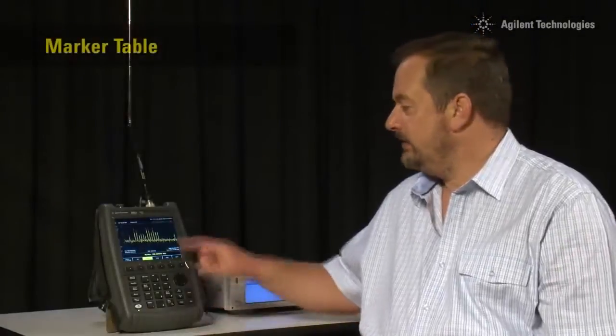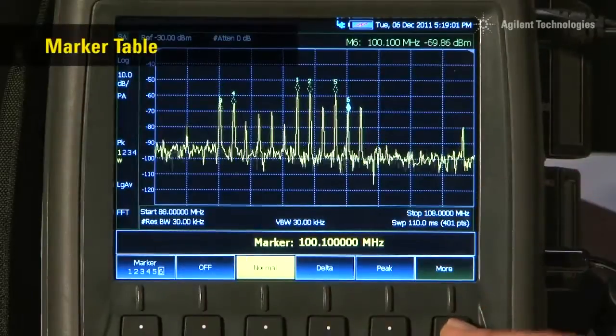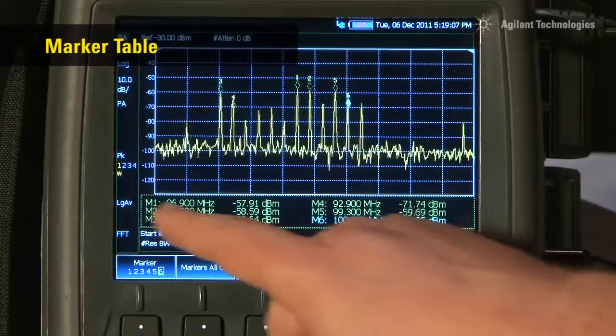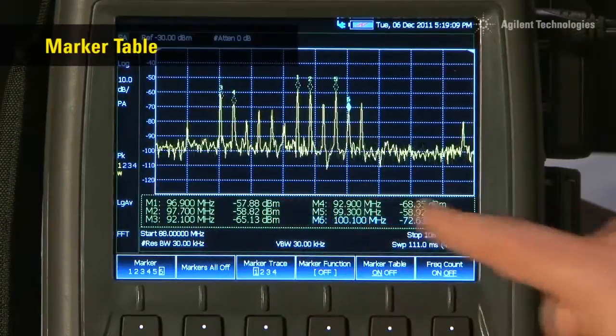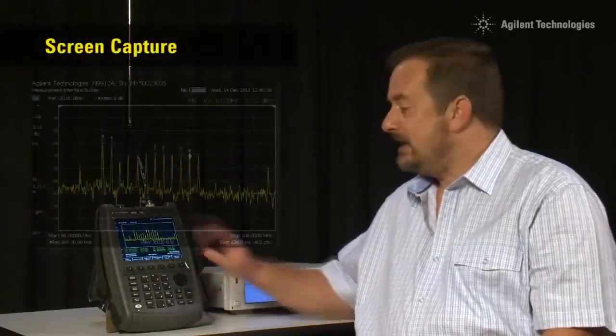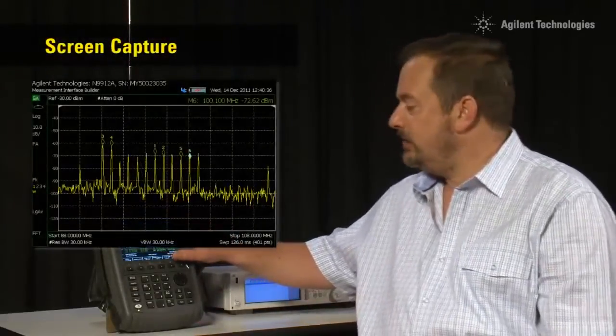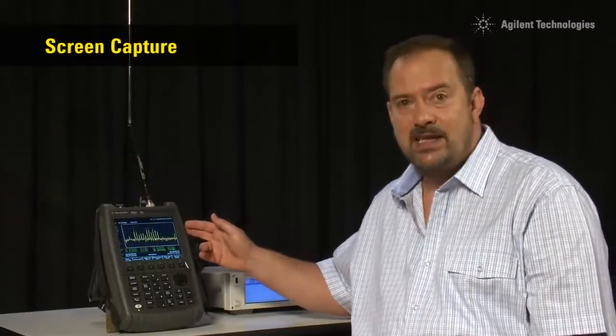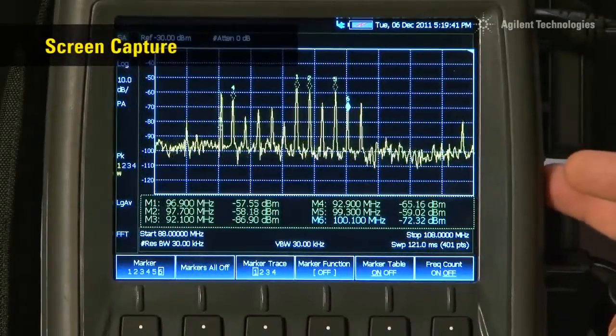Here you can see I have turned on all six markers, and if I press the more button, we can now turn on the marker table, which shows the frequency and amplitude levels of all six markers simultaneously. We can now capture that screen and save it as a JPEG file, either to the internal memory, to a USB memory stick, or the mini SD card.